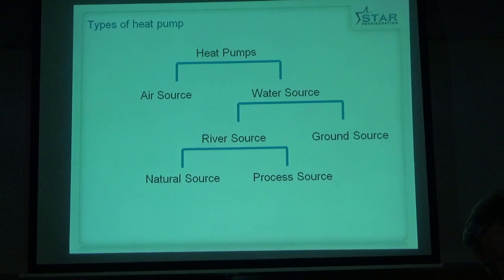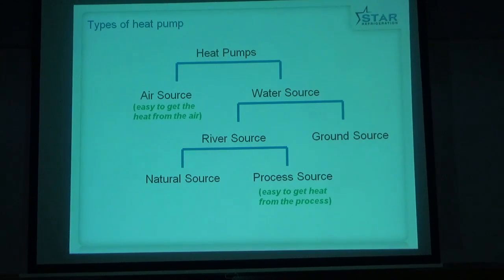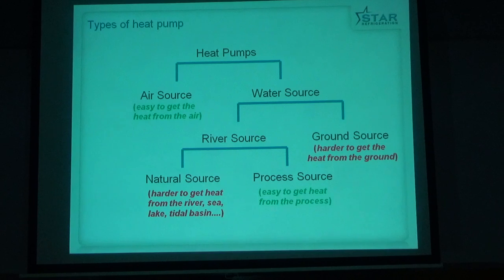I'm talking about. So we can also characterize them by air source, easy to get the heat out of the air. You saw the big box that I showed you, the 450 kilowatt, it's just got fans on the top and air blows through it, that's all you have to do, it's dead easy. Process source, as I said, is given to you on a plate, the water's being pumped anyway, all you need to do is put a heat exchanger into the water line and you've got your heat source. So they're the easy ones. Ground source and natural source, you have to think a bit more about it, it is a bit harder. So we can characterise them that way.